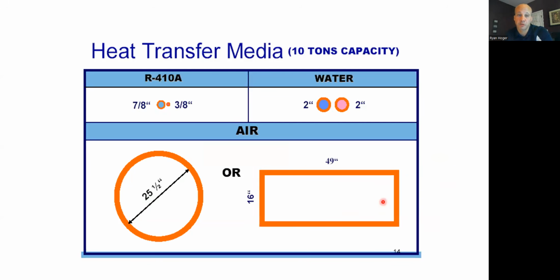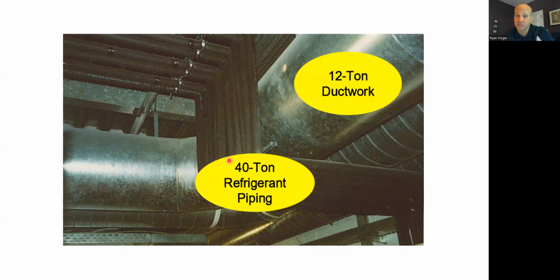If I look at it from that perspective, a 16 by 49-inch duct can carry a certain amount of capacity, 10 tons of cooling. I could do 10 tons of cooling with 2-inch hydronic water lines, or I can do 10 tons of cooling with even smaller than 1-inch refrigerant lines. Right, so I can move a lot of energy through a building without taking up very much space. This is 12 tons of cooling running through a duct system. This is 40 tons of cooling running through refrigerant piping. It takes up way less space.